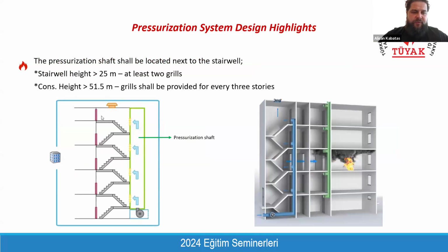It is achieving a good pressure equivalence within the stairwell. Otherwise, if you just give air from the top, the higher floors will have relatively high pressures, while the lower floors will have less pressure, and it will cause a stack effect, and smoke can interfere. Smoke can go through the stairwell, and it will cause a life safety problem.